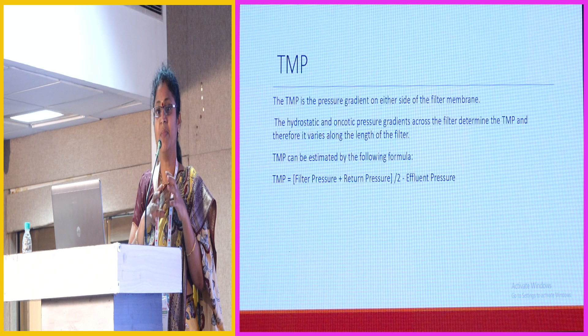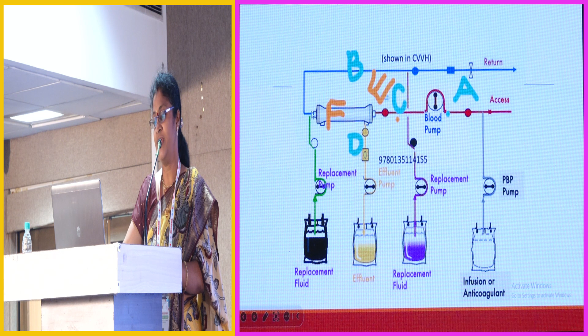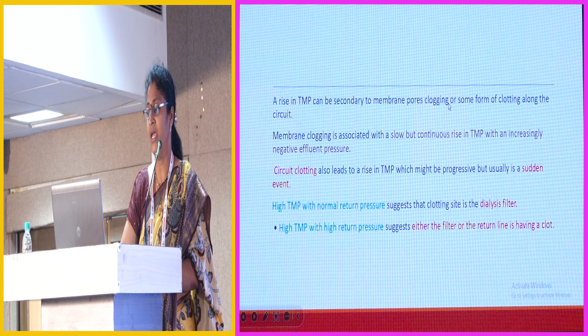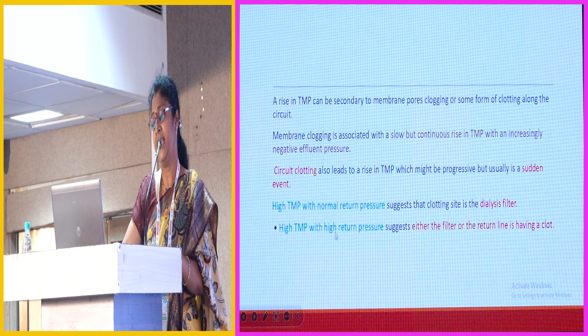So TMP represents the pressure across the filter. So F is the TMP. A rise in TMP is secondary to membrane pores clogging or some form of clotting along the circuit. High TMP with normal return pressure means the catheter is very good. Return pressure means your arterial side is very good. That means there is some problem with the filter. Suppose you see high TMP and high return pressure, that means either the filter or the return line also has a clot.